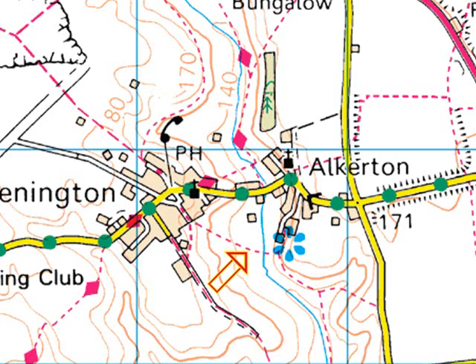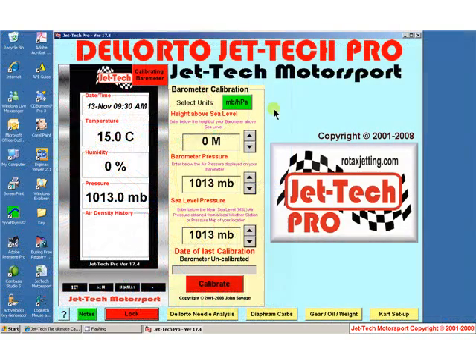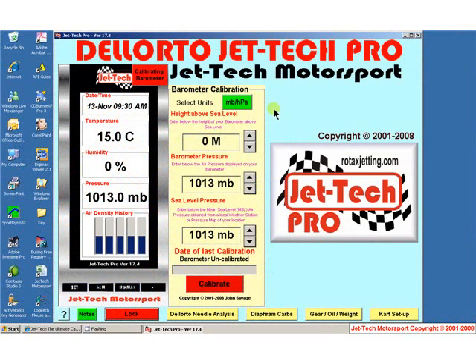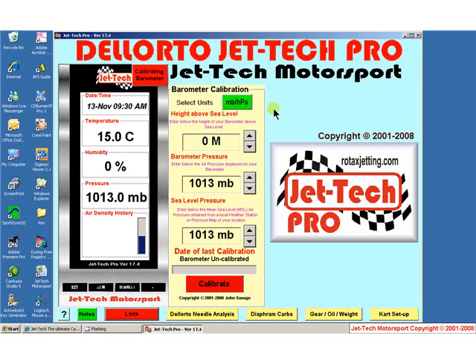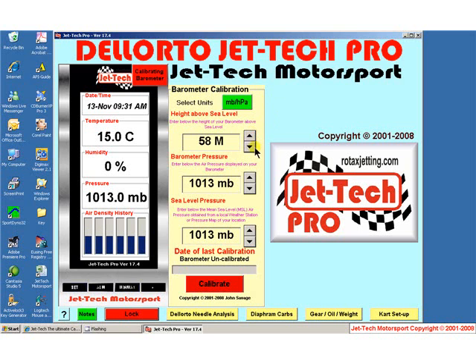you will see that Shenington Kart Club is at an altitude of 140 metres. This information is readily available across the internet, or perhaps your local library and an ordnance survey map of your location. Please remember that if you are conducting this calibration in your home office, and that is on the second floor of your house, then you need to add that height difference to your ground level height. I have determined earlier that my location is 51 metres above sea level.